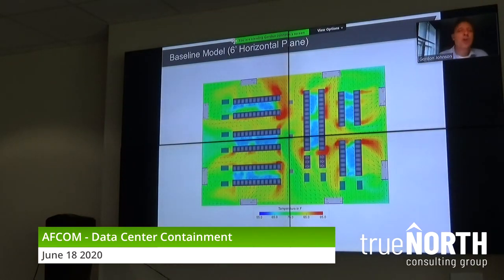This is the 6-foot horizontal plane with all the CRAH units running. And I apologize, I say CRAH and CRAC interchangeably. That's not really true. But here's a look at all the CRAH units, and they're all running right now. Notice the hot air at 6 feet. It's going around the edge of the cold aisles, into the cold aisles, and it's going over the top of the racks.